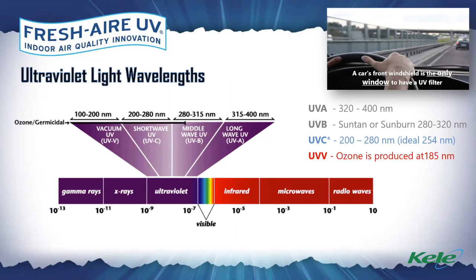But ultimately, we're taking that UVC light, that same wavelength at the 254 nanometer wavelength of light, and we're incorporating it into the HVAC system. So we're naturally doing inside the HVAC system what's actually happening in the upper atmosphere, addressing the biologicals. A fourth wavelength of light, known as UVV, at 185 nanometers, is an ozone producing wavelength. Now, we do not produce the 185 nanometer. Our lamps are doped not to go below the 254 nanometer. So rest assured that our UV systems are zero ozone emitting, specifically delivering UV at the 254.